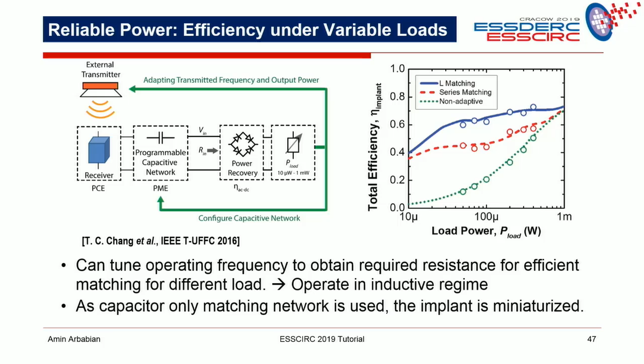So remember I said that the implant or the piezo is inductive from short circuit resonance to open circuit resonance, so I can operate it anywhere in that frequency range if I have the right matching network. So what we did in this work is tune the frequency and the matching network to maintain a flat efficiency across usage. I go from a milliwatt down to about 50 microwatts, and my efficiency is still above 60% by changing the frequency range and the matching network. That's one of the things we do adaptively for implants that have a very wide power usage range.